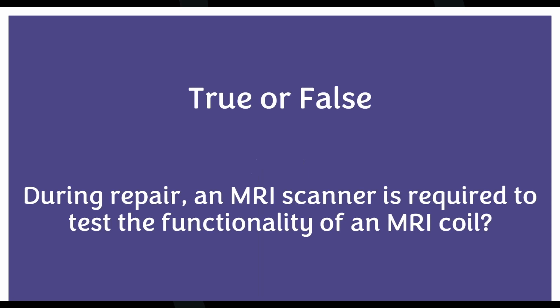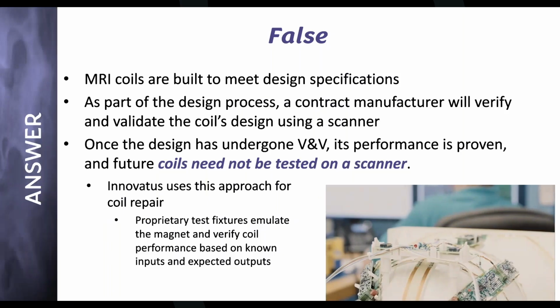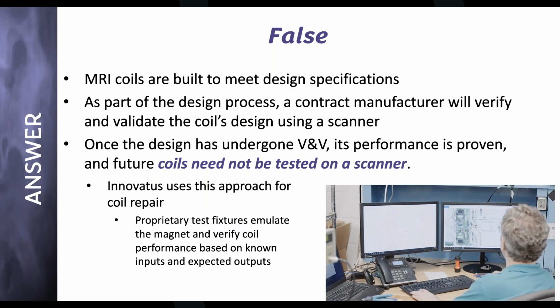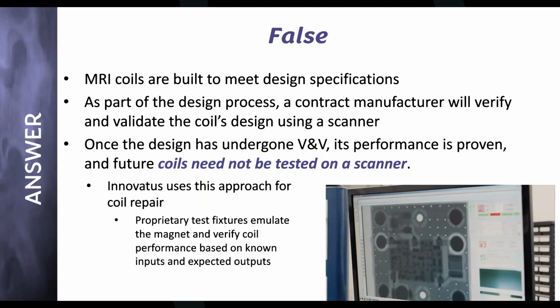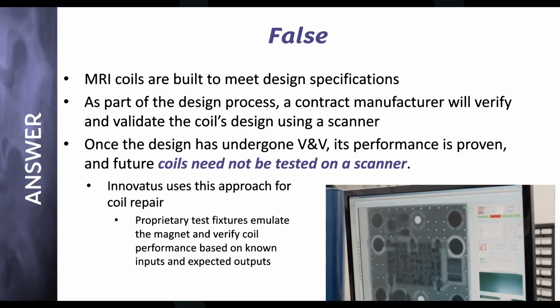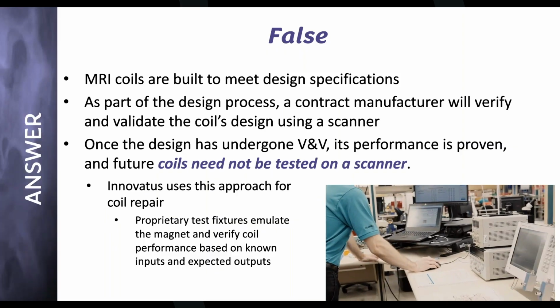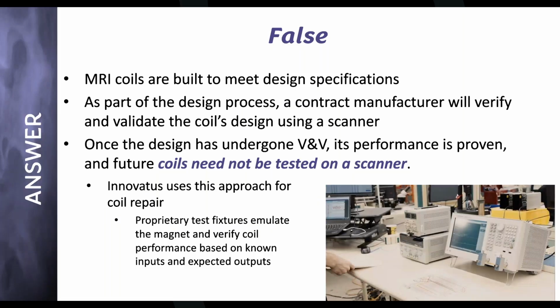True or false? During repair, an MRI scanner is required to test the functionality of an MRI coil. False. So you were correct. It is false. An MRI scanner is not required in the repair of a coil to test it.